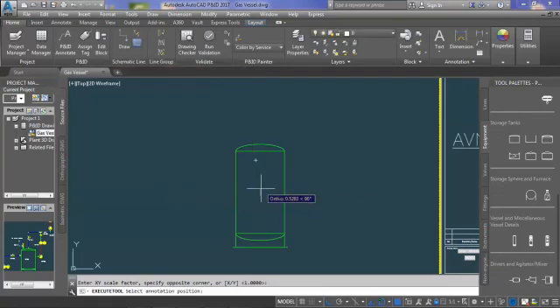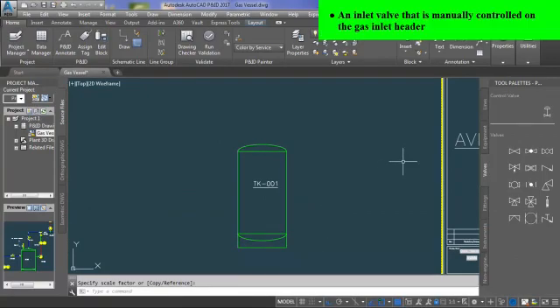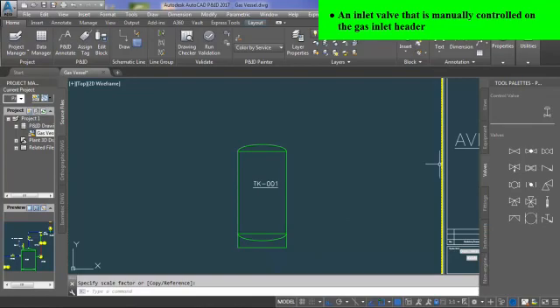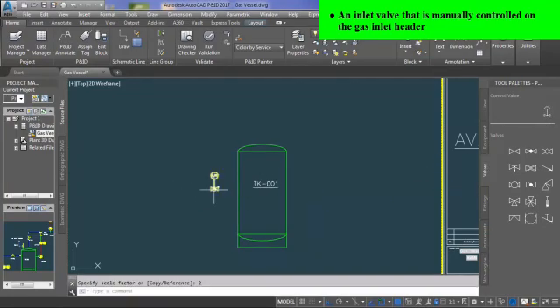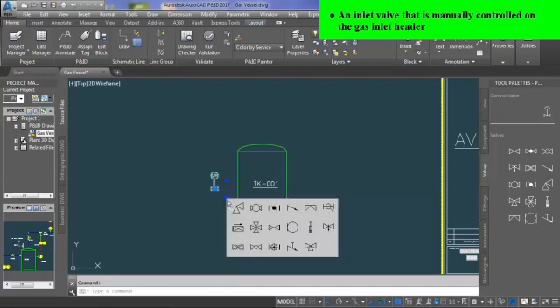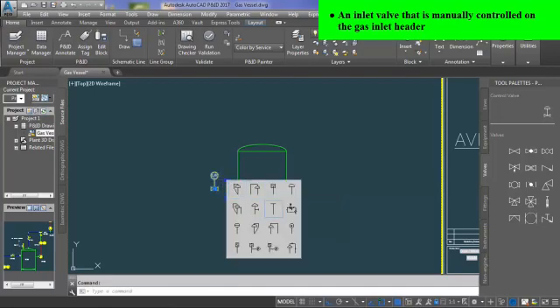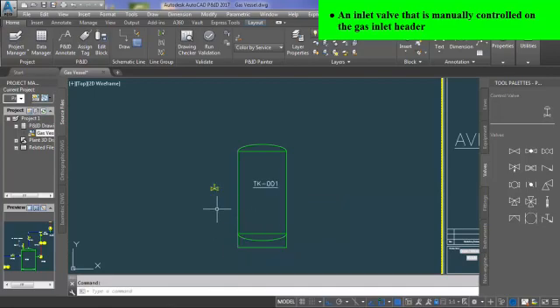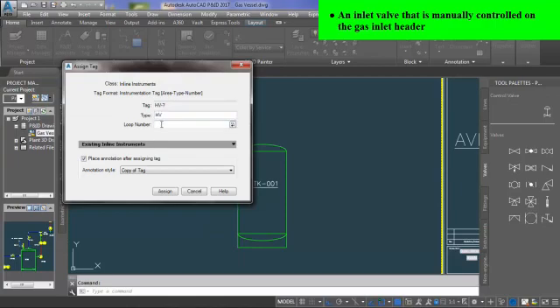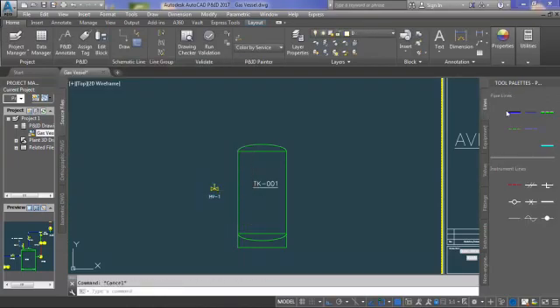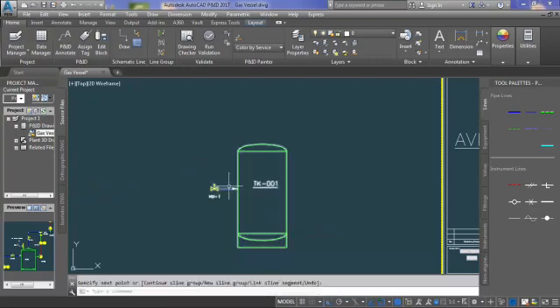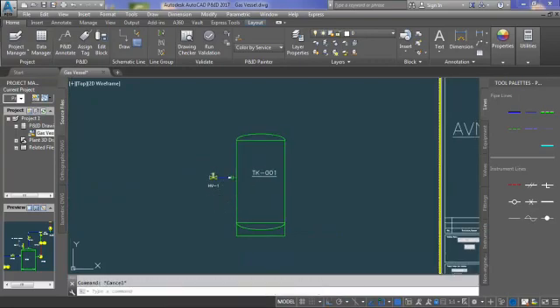Place the tag to complete this step. After this, the next step is to insert instruments. The first instrument is a manually controlled valve on the inlet pipeline. From valves, select control valve and convert it into a gate valve with manual actuator. Then right-click on the valve to open the tag assign window and tag it Hand Valve 1 or HV-1. After that, add primary pipeline from the lines tab for gas inlet into the tank.